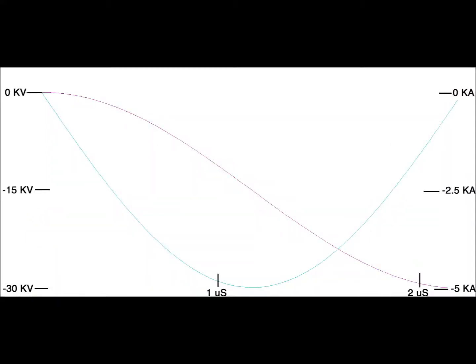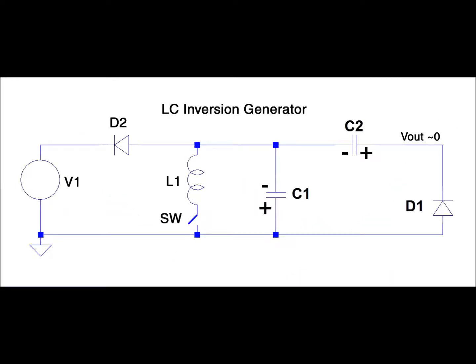This shows the voltage and current waveforms in the thyratron circuit. When the thyratron is triggered, the current rises to a peak value of approximately 5,000 amps and returns to 0, whereupon the current stops flowing, as it would in a thyristor circuit. This is what prevents discharging the capacitor C1 in the inversion generator. Notice also that the voltage on the inversion generator goes from 0 to approximately minus 30,000 volts in the 2 microsecond time period.